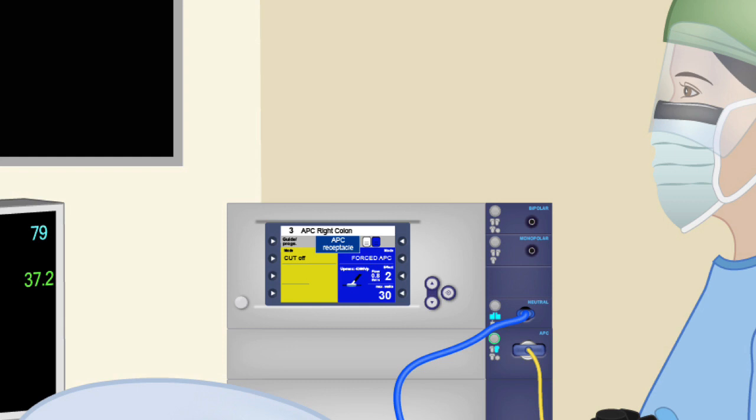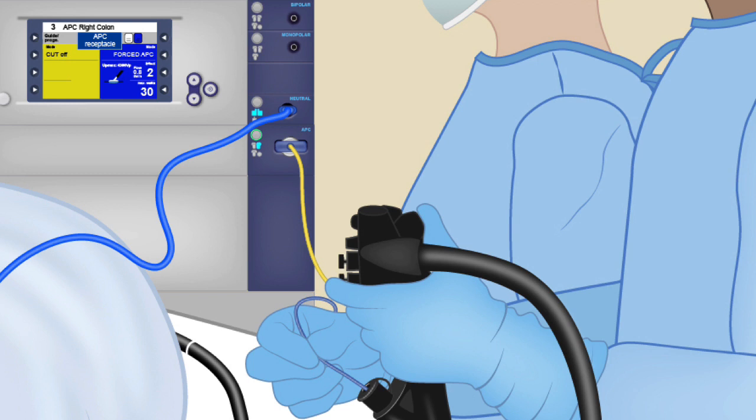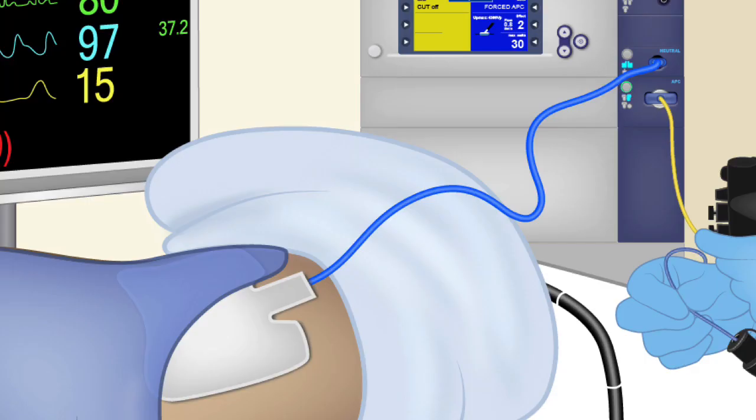The electrosurgical generator allows delivery of both the gas and the current. Both go through a catheter that we insert into the endoscope to the field where we deliver the gas and the current. Being a monopolar type of electrosurgical circuit, the patient needs a returning electrode back to the electrosurgical generator to complete the circuit.